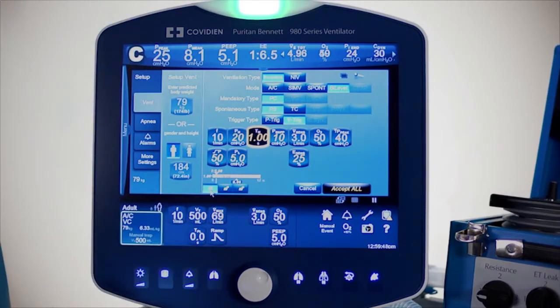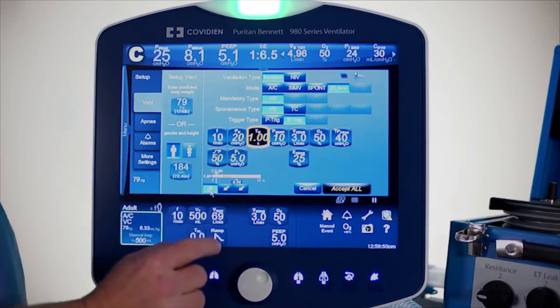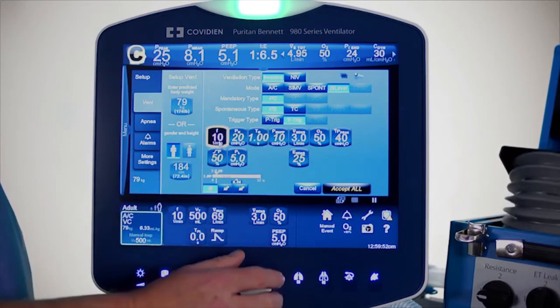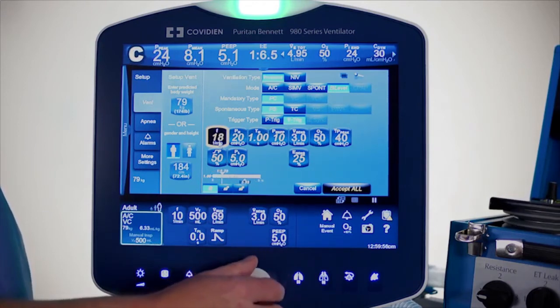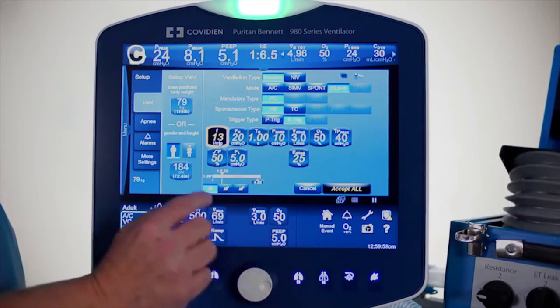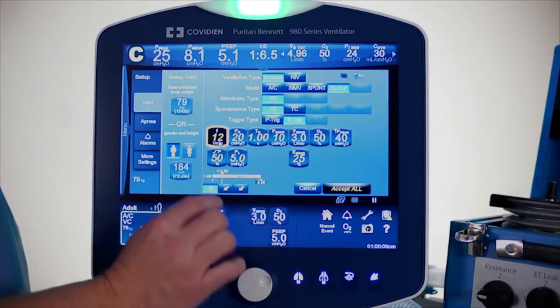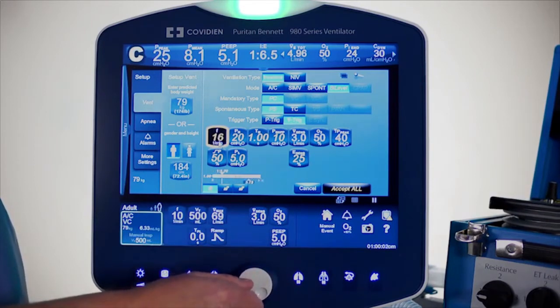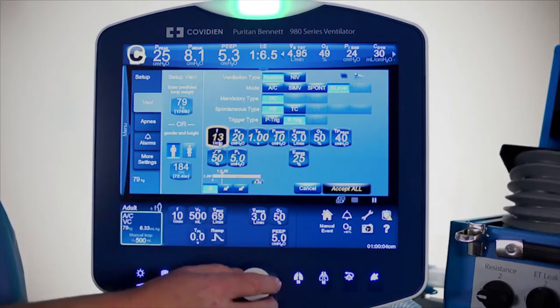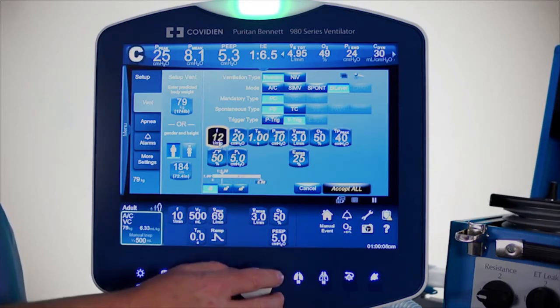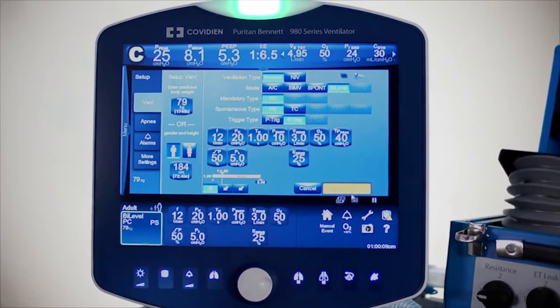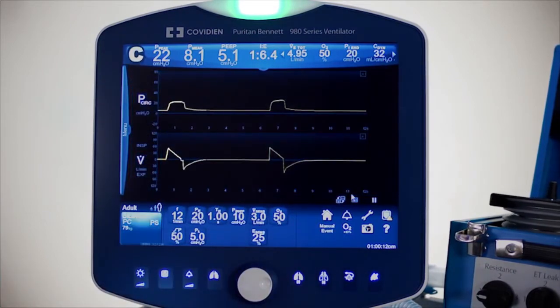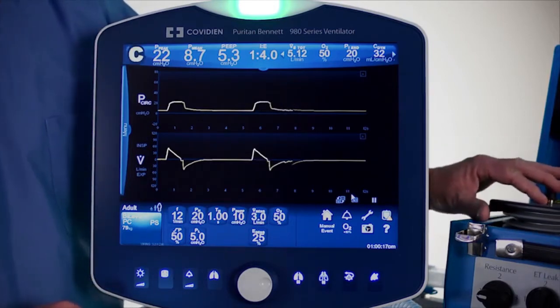When the lock is set for inspiratory time, any time someone changes the rate it does not affect the inspiratory time. As I'm adjusting the rate, you'll see that the inspiratory time stays locked. With those settings, let's go ahead and accept them.